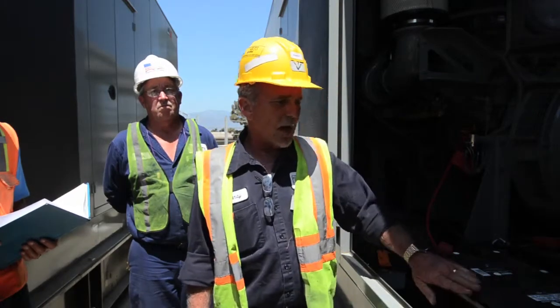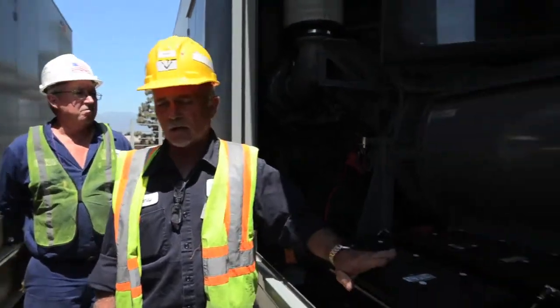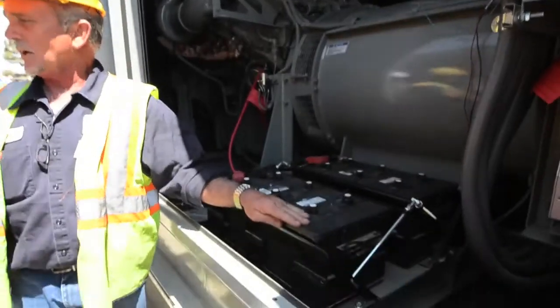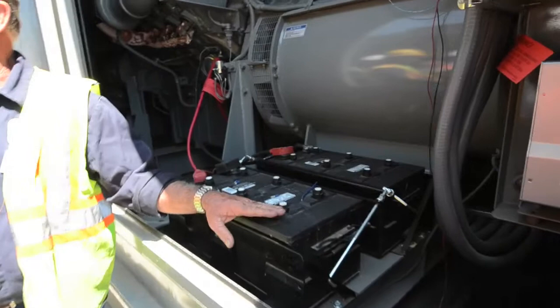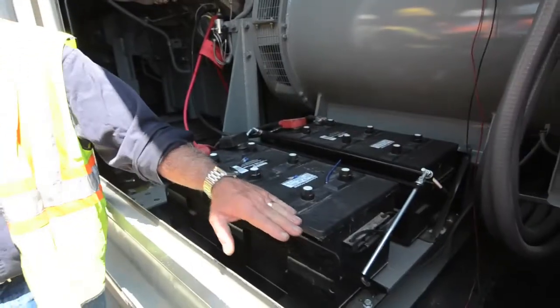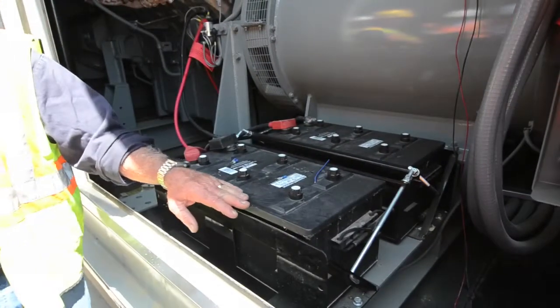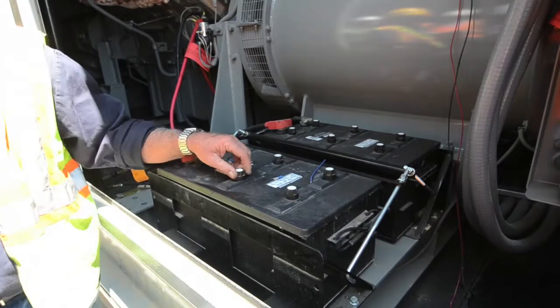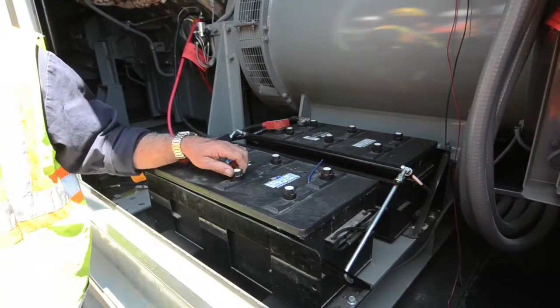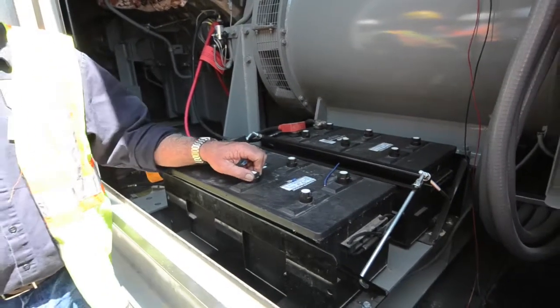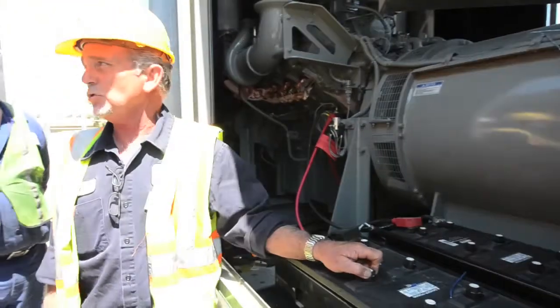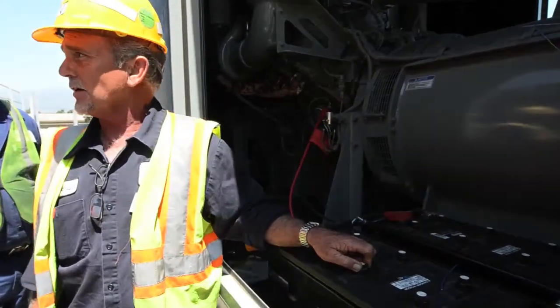As I move forward, the batteries, there are two sets of these 8D batteries, two on this side, two on the other side. They are the heartbeat, the main power for the whole generator system. If you'll notice, these are the older lead style maintenance type batteries. We do not recommend that you use maintenance free batteries in any generator.